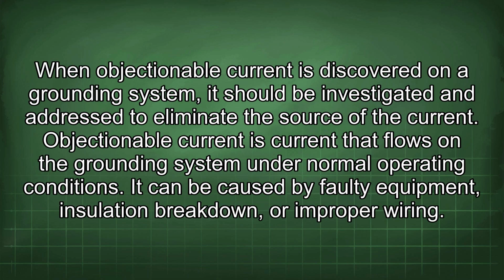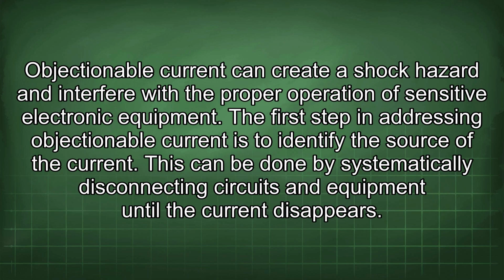When objectionable current is discovered on a grounding system, it should be investigated and addressed to eliminate the source of the current. Objectionable current is current that flows on the grounding system under normal operating conditions. It can be caused by faulty equipment, insulation breakdown, or improper wiring. Objectionable current can create a shock hazard and interfere with the proper operation of sensitive electronic equipment.